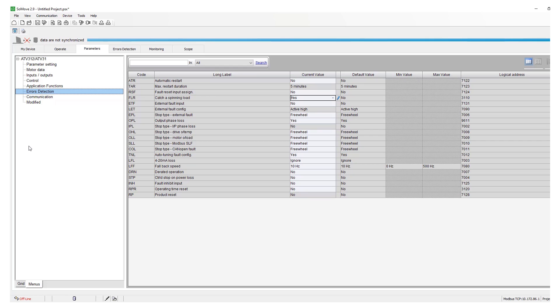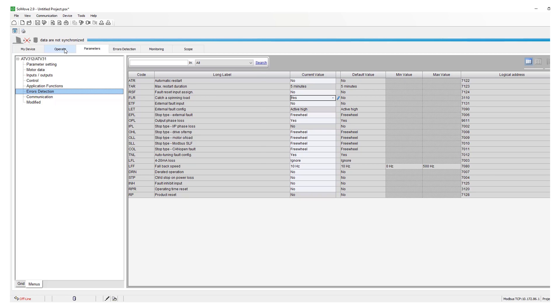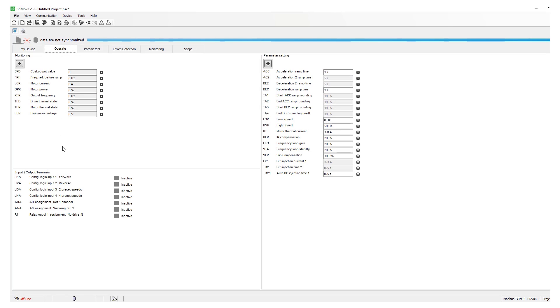The motor current being pulled by the motor is also important to check. If you have SoMove connected you can check the LCR motor current, see how much current the motor is pulling. Make sure it does not exceed the drive rating or the motor rating. This LCR parameter is also available through the keypad as well.